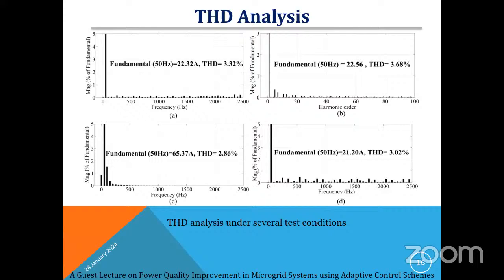If you see the second one, this is the voltage swell, from 28 to 3.68, and next the third figure, sag condition, 2.86, and the fourth figure, a dynamic load condition. In the dynamic load condition also we have reduced from 28 to 3.0%. So in all conditions we got less than 5%, and all THD values are within the IEEE 519 standard limits.